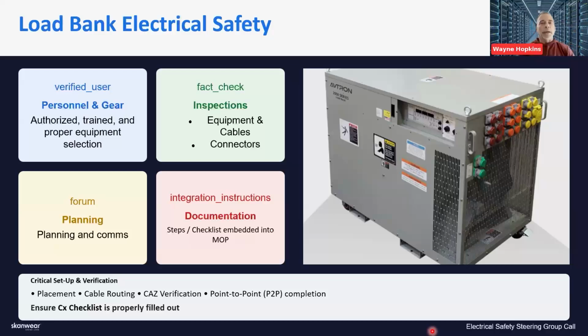All of that should be embedded into a MOP, so as workers go through it they hit the point that says: check cable conductors, have point-to-points been completed to verify cable conductors to load banks are in proper placement.